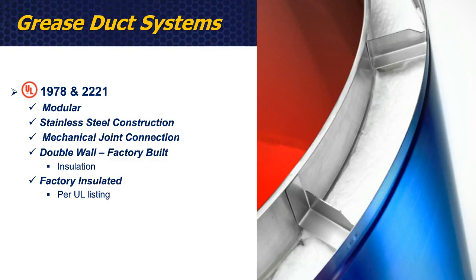Factory products are UL 1978 and 2221. I mentioned this before. Modular construction, stainless steel, a mechanical joint connection that can be easily done in the field. They're double wall and they're factory built. So the construction is done in a controlled environment in a manufacturing facility, and the insulation is all installed at the factory per the UL listing to make sure we've got adequate coverage. And then it's protected with an outer shell to make sure that it stays intact in transportation, during installation, and even testing in the field.